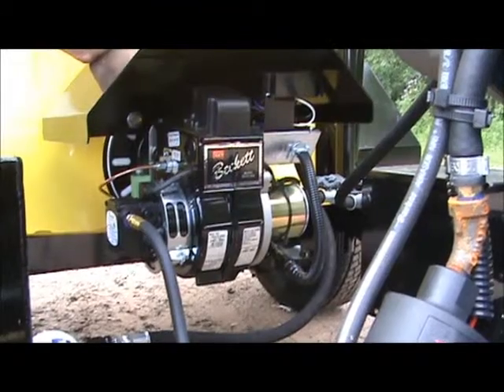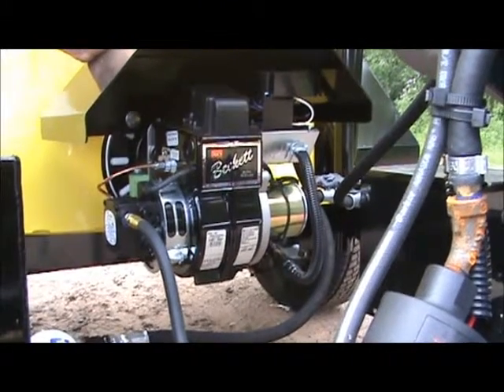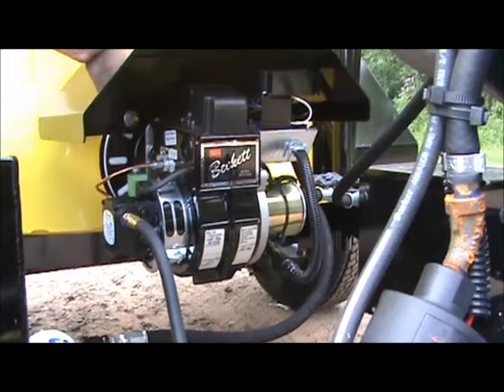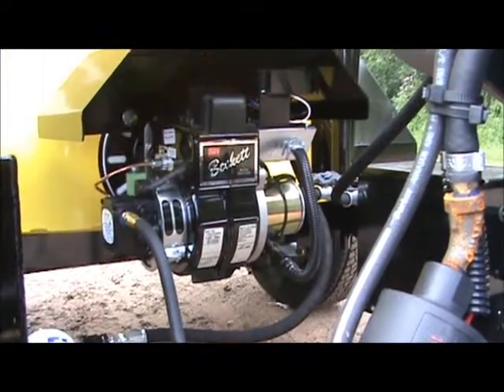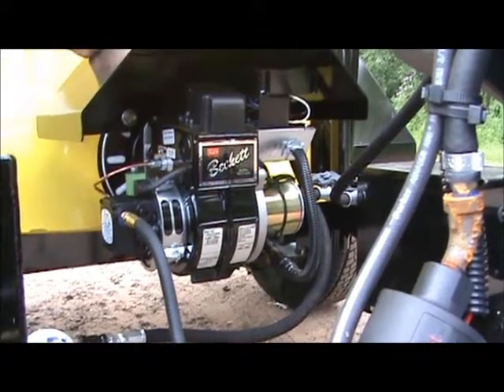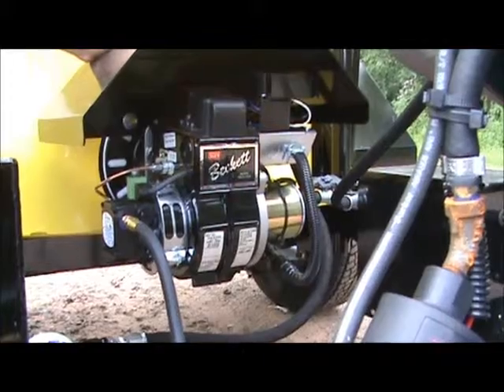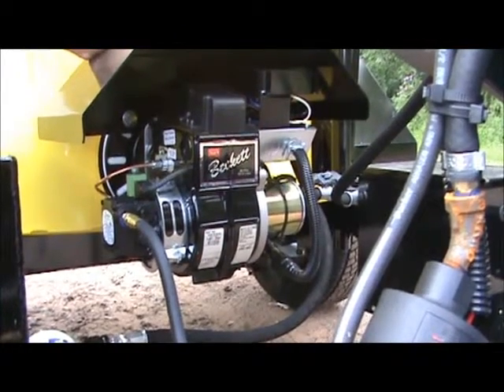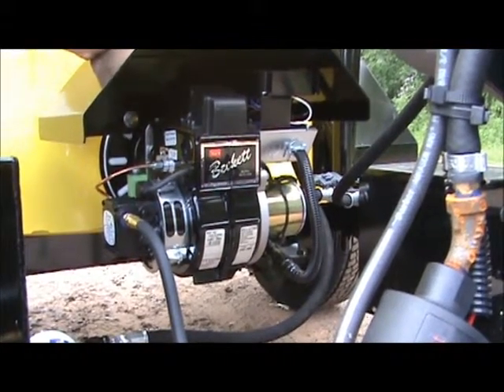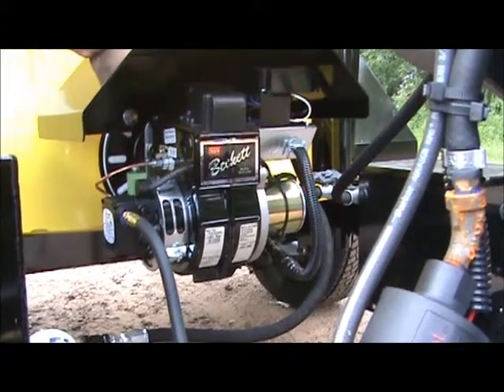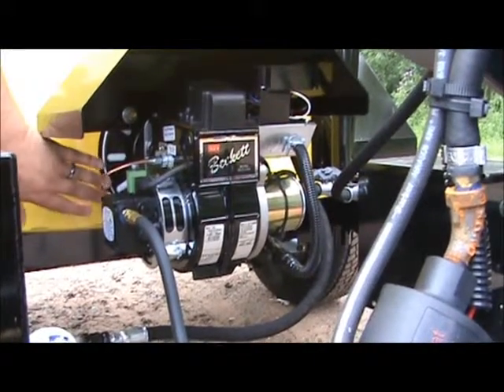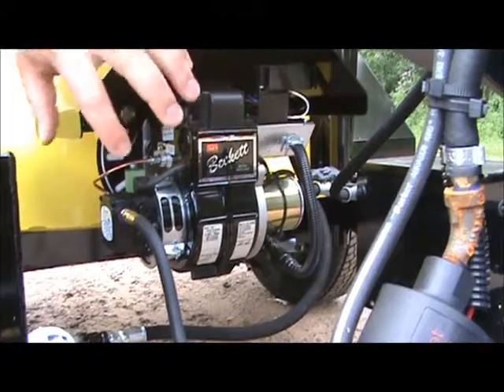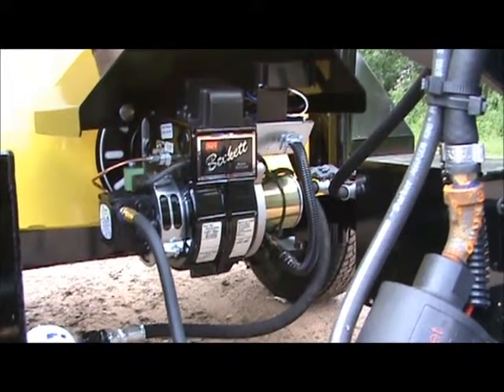We do want you guys to pull the burner out at least yearly and inspect the inside liner. Behind this burner is a stainless steel liner. That's going to prevent our tank from burning out, and it also helps establish flow, a good burn chamber for the burner system. So to inspect that, there are 4 nuts on the back side of the burner. You'll take the nuts off and the burner will come out. You stick a flashlight in there and take a look.